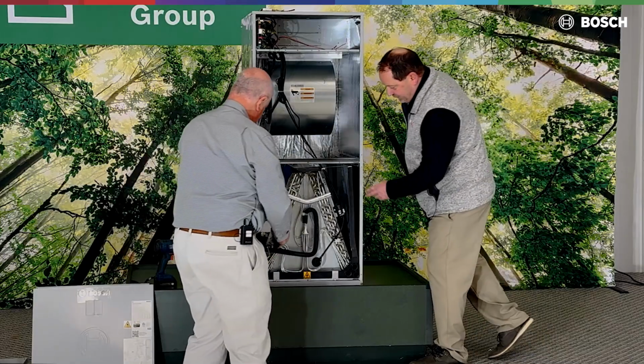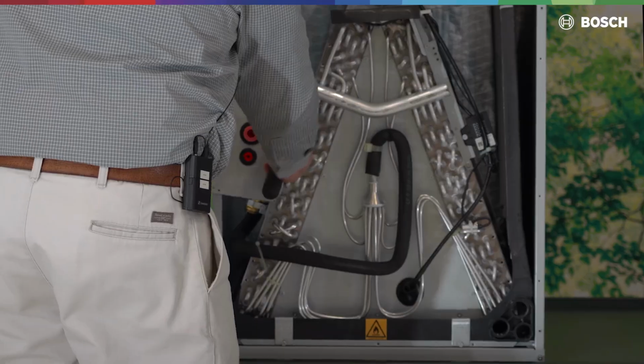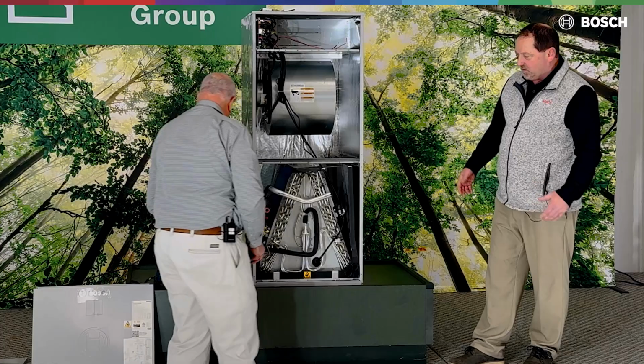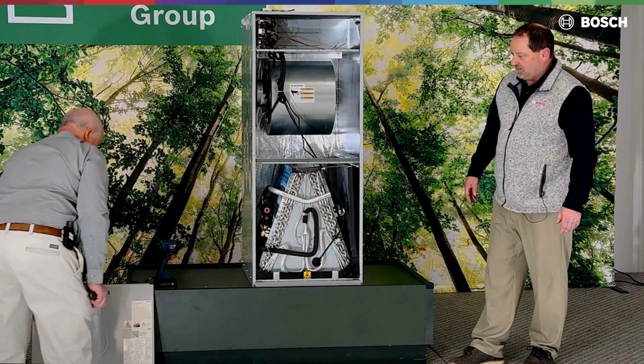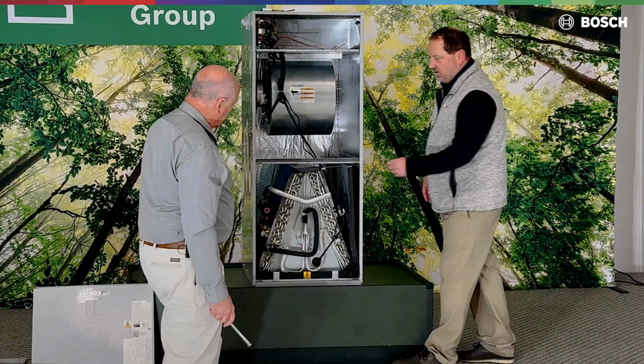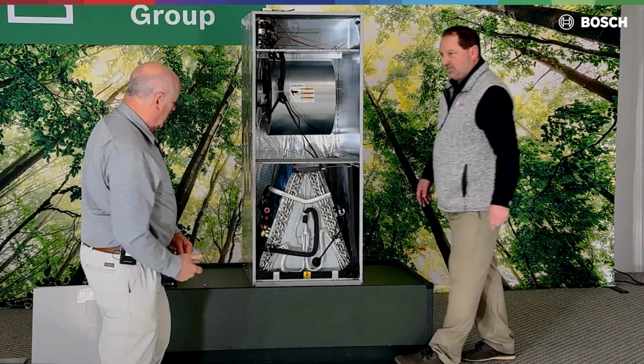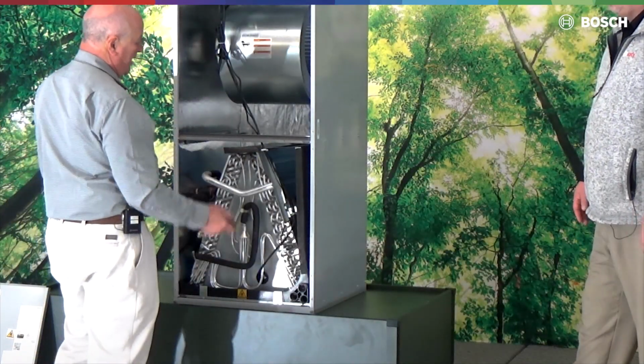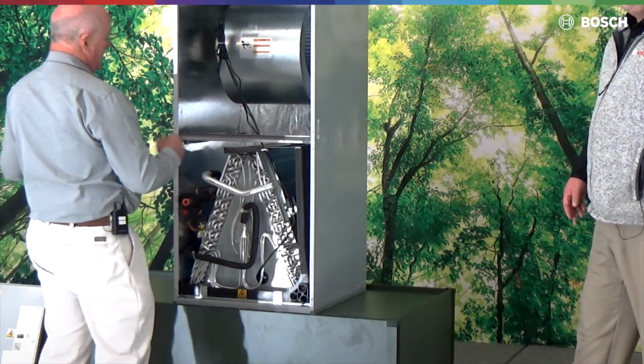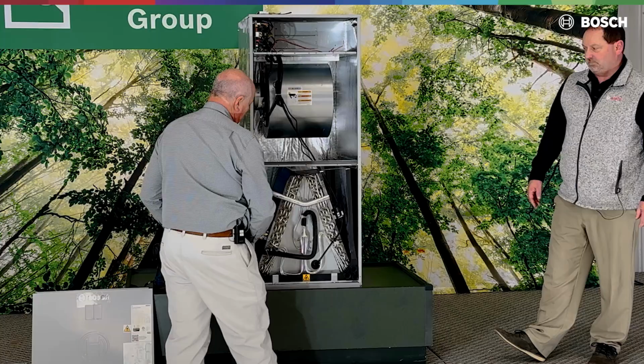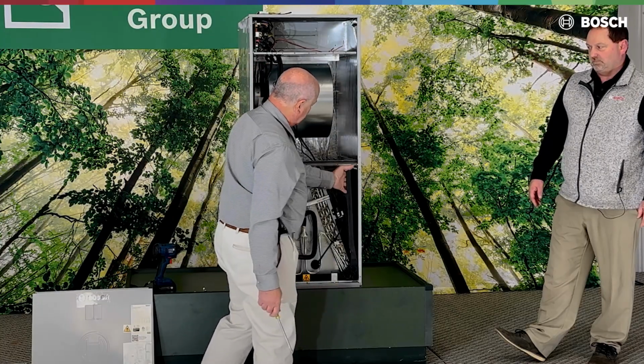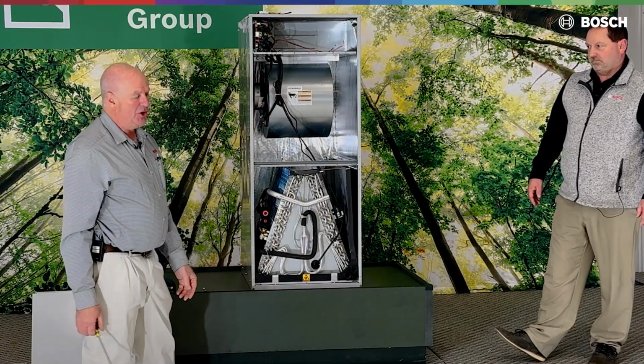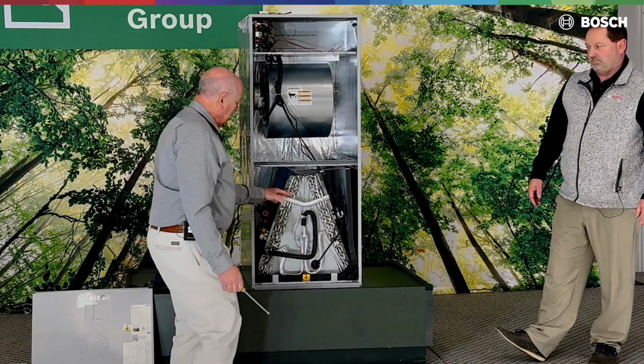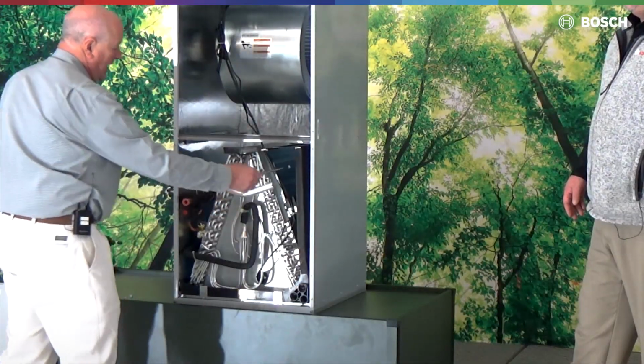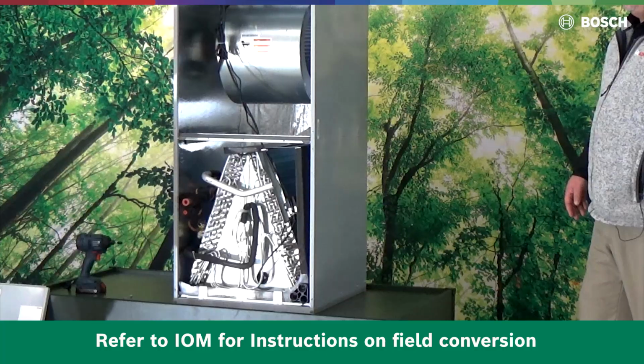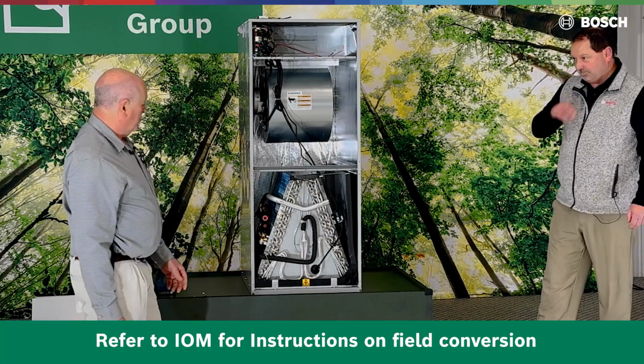Now that we got the covers off, there's a few things that need to take place before we can actually take that coil out. So this coil is a multi-poise coil. We can go, as we see now, as a vertical upflow, or we can lay it down on the right, and it would be a right intake, left blow. Condensate pan is already set up for that application. If we were to make this a left blow, we would have to change the coil around so the condensate pan is on the bottom. Make sure we have that condensate pan set up properly.